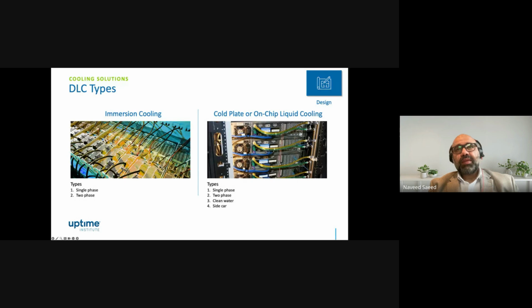On the cold plate side, it's on-chip liquid cooling. There are four categories. Again, single-phase liquid, and multiple types of single-phase liquids are available out there in the market. Two-phase liquid, dielectric fluids, and clean water, deionized water, water-glycol mix, and the sidecar arrangements are out there. So again, whatever kind of infrastructure you are going to put there, your cooling has to be compatible with that.